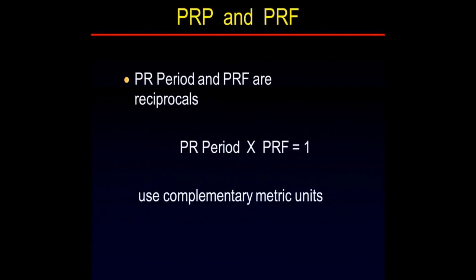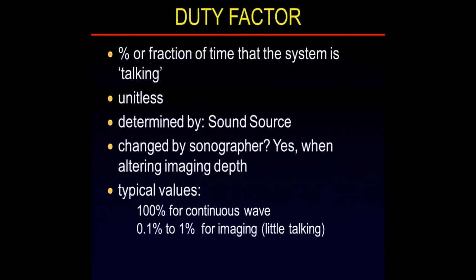Okay. So pulse repetition period and pulse repetition frequency are reciprocals. Duty factor is simple. It's just the percentage of time the ultrasound machine is talking. I already told you that the system listens most of the time and talks just a little bit, so it's always a low number. It's always less than 1%, and it's even lower when we go deeper.